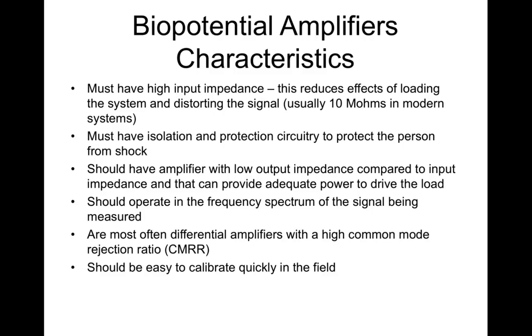The first characteristic is that the amplifier must have a high input impedance. This reduces the effects of loading on the system or circuit, which would distort the signal. Typically, you want 10 megohms of input impedance in a modern biopotential amplifier system. That high input impedance means that whatever the measurement system adds as an additional load won't pull current from the measurement and impede or interact with the measurement itself.